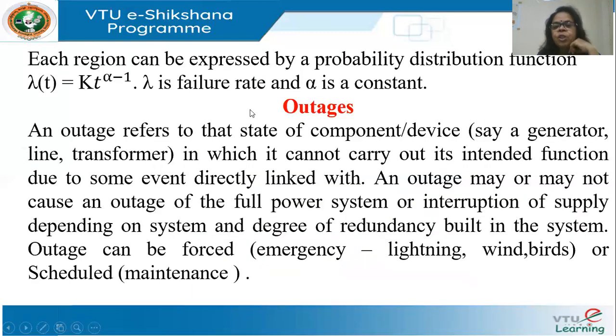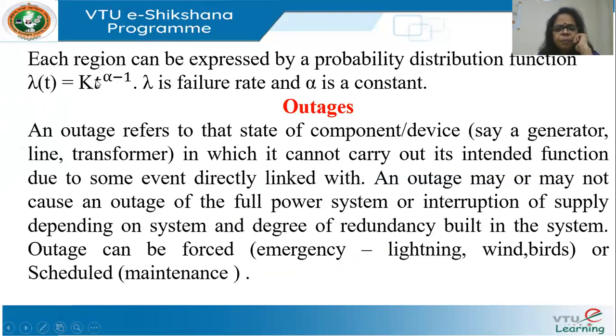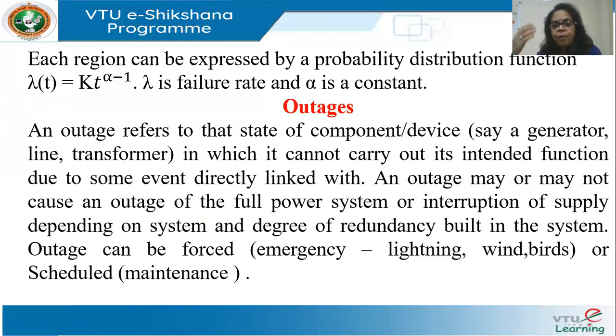Each region of the bathtub curve can be expressed as a probability or distribution function, because reliability is all about probability — you can never say exactly when a product will fail. The failure rate is commonly given by the expression: λ(t) = K · t^(α−1), where K is a constant, α is also a constant, and λ is the failure rate. Different equipment will have different failure rates, and the failure rate can be updated based on the age of the equipment.